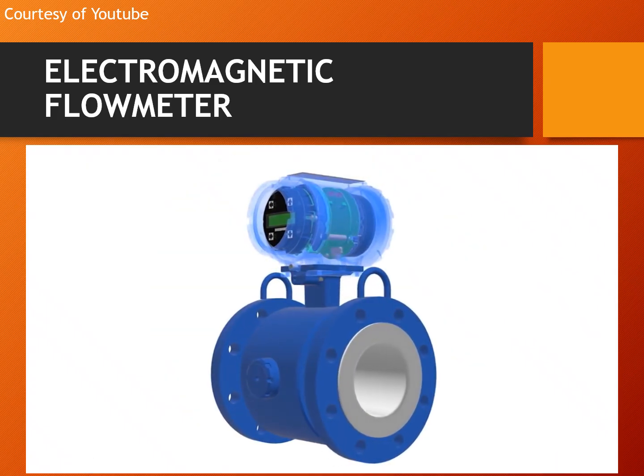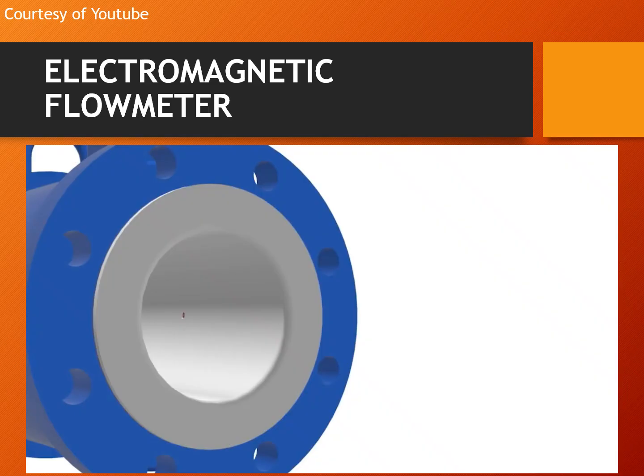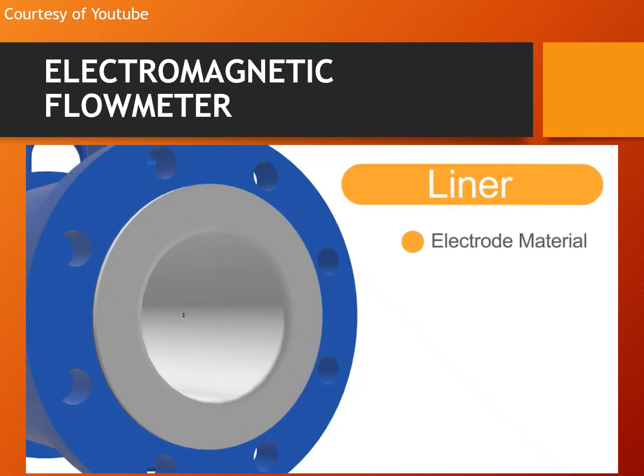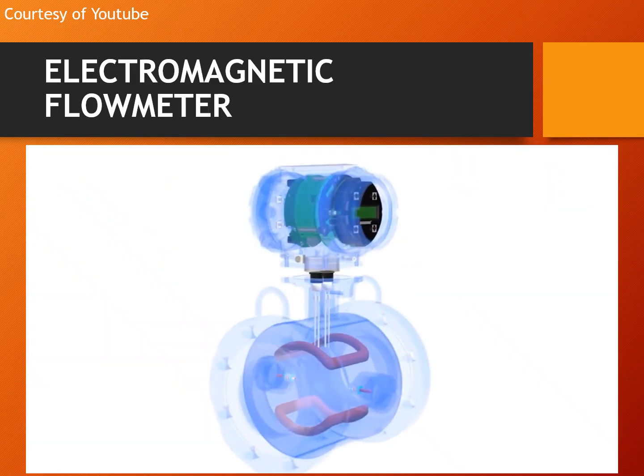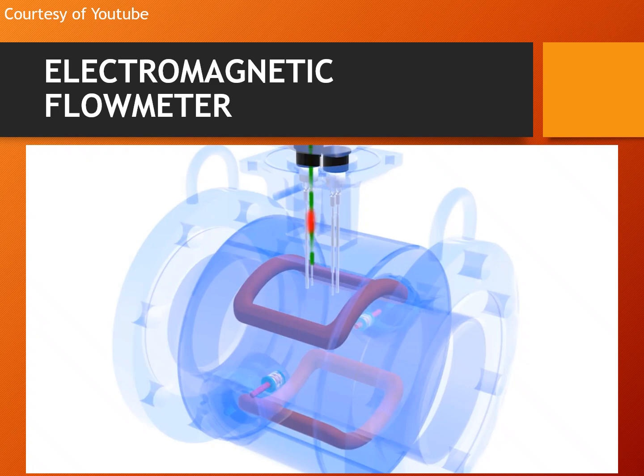To prevent electrical shorts of the sensing component circuitry, the pipe of the flow meter is lined with a special material known as a liner. This liner, along with a selection of the proper electrode materials, is important to protect the sensor against abrasive and corrosive chemicals and solids. One historical limitation of magmeters is the impact of process noise.